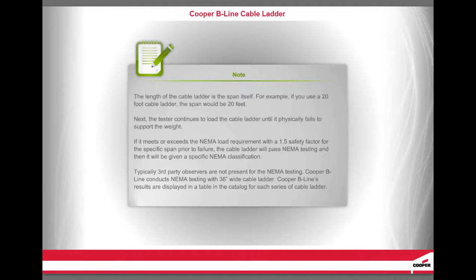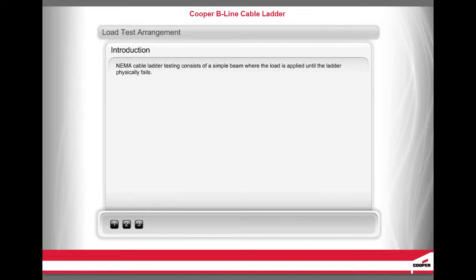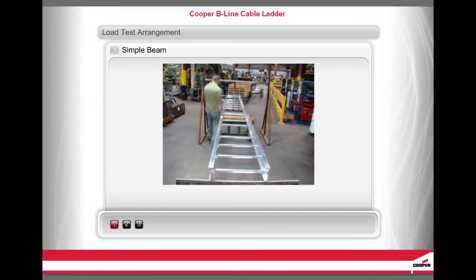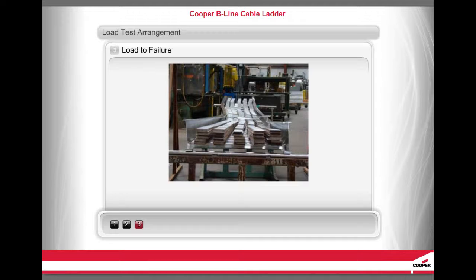Typically, third-party observers are not present for the NEMA testing. Cooper B-Line conducts NEMA testing with 36-inch wide cable ladder, and results are displayed in a table in the catalog for each series of cable ladder. NEMA cable ladder testing consists of a simple beam where the load is applied until the ladder physically fails: simple beam, load applied, load to failure.